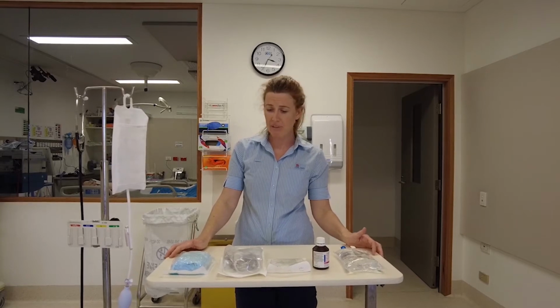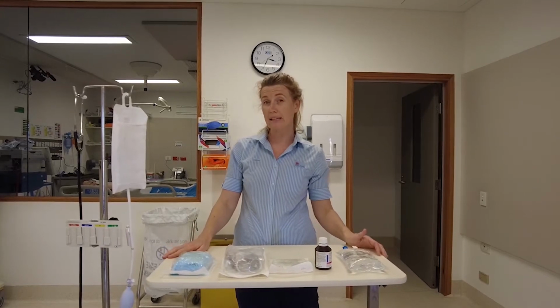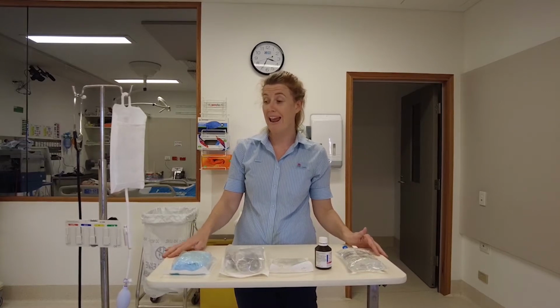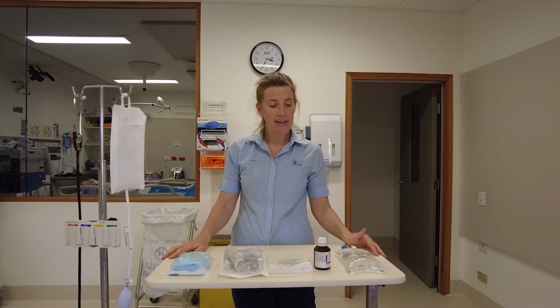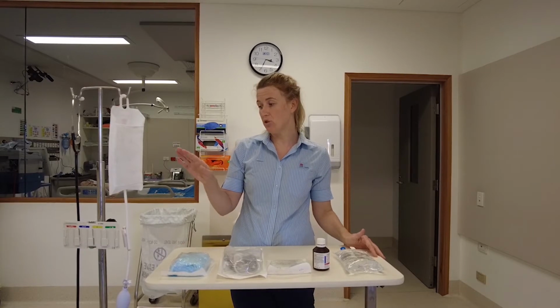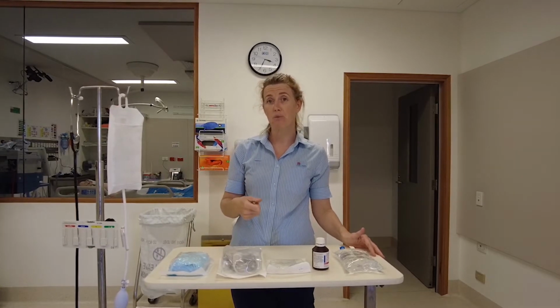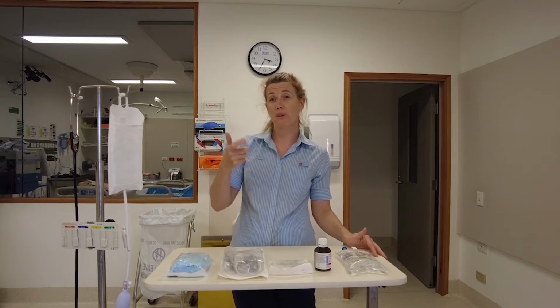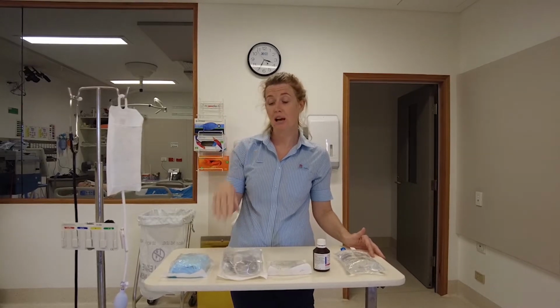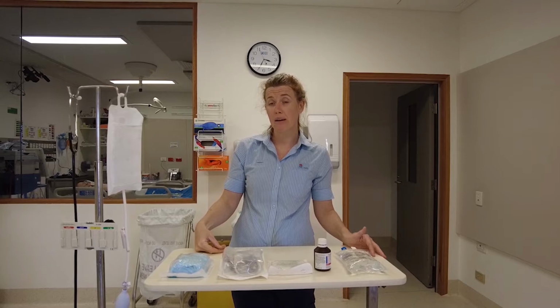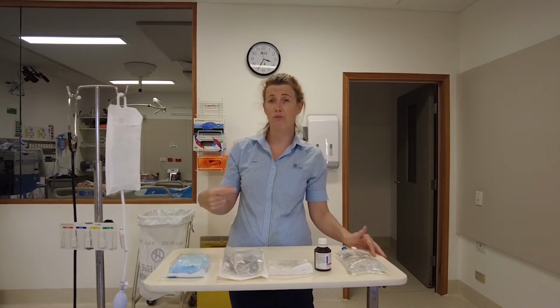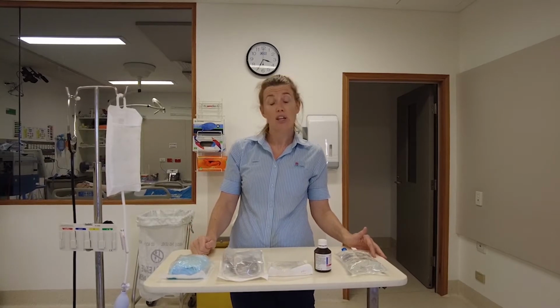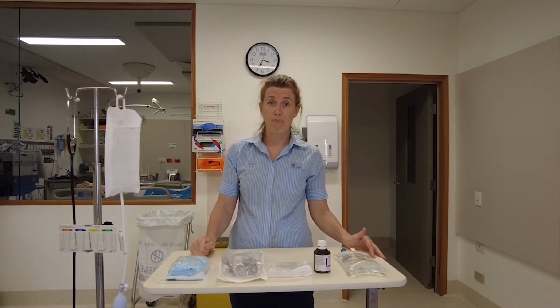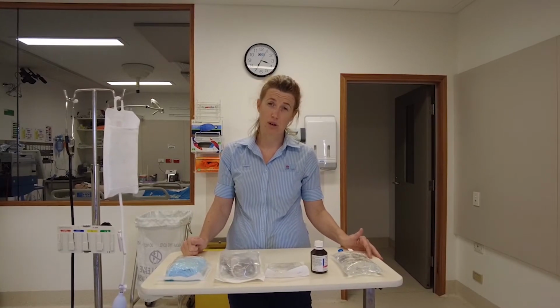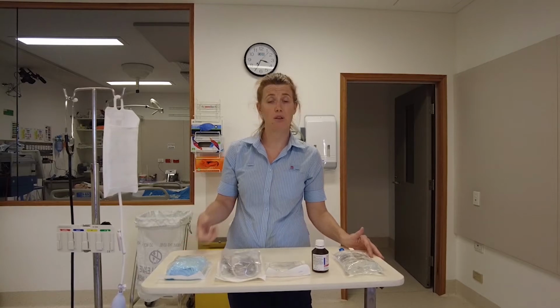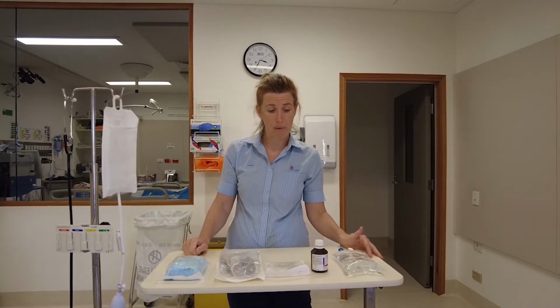The second thing that's really important is the actual priming itself and ensuring that you don't entrain air into the system. And that's because air bubbles in your transducer line actually affect what we call damping, which is related to the trace that you see on the monitor. And even one or two tiny little air bubbles can affect this, and that's going to affect the accuracy of the numbers that you're being shown and that you're basing other treatment decisions off. So it is really important that you prime the line in a way where you don't get any air bubbles.